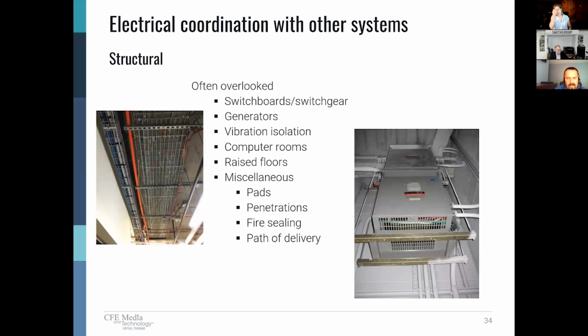So one critical aspect of coordination that is often overlooked with electrical installations is our coordination efforts with structural. I mean, we're putting in switchgear and switchboards and generators. Often this equipment is on upper decks. It's up on upper floors, can end up on the roof in a roof penthouse, for example. And these items weigh in the tonnages. So it's important that these things be accommodated accurately, that the load-bearing capacity is within the structural system. It needs to be coordinated.